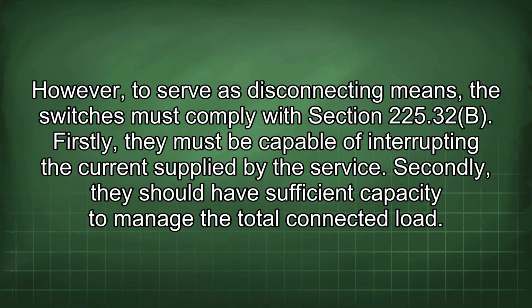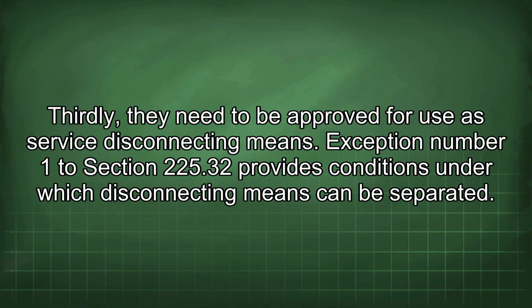However, to serve as disconnecting means, the switches must comply with Section 225.32b. Firstly, they must be capable of interrupting the current supplied by the service. Secondly, they should have sufficient capacity to manage the total connected load. Thirdly, they need to be approved for use as service disconnecting means. Exception number 1 to Section 225.32 provides conditions under which disconnecting means can be separated.